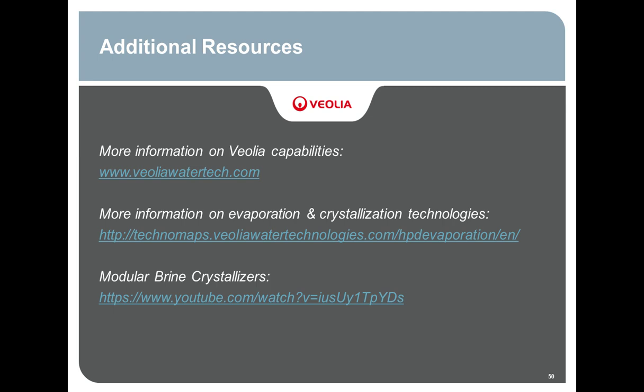Great. Next question for you here. What is the typical TOC reduction of the distillate from an evaporator and crystallizer? Well, TOC is a tough one. Usually if you have organic compounds in the feed water, you're going to get some fraction of them to wind up in the distillate water. So it's just a matter of what organic compounds are in there, how volatile they are, how their volatility compares with that of water. But typically, if you have organics in the feed, you'll probably see some organics in the distillate as well. So it's a matter of how much you can stand in your reuse processes.